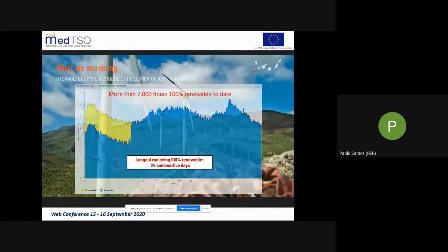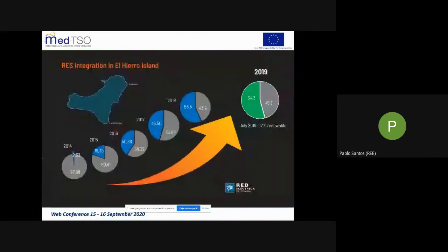What we have achieved so far in El Hierro Island with this storage system is several runs being 100% renewable, covering the island demand with a mix of wind and hydro. The longest run has been 24 consecutive days, that was last year, 2018. And since the very first day the system entered into operation, we have reached more than 7,000 hours being 100% renewable in El Hierro Island.